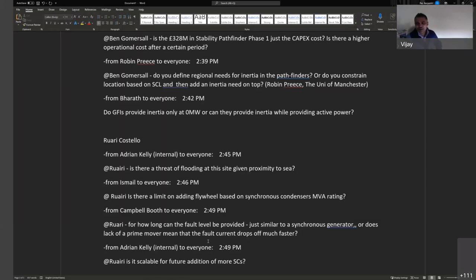How do you start a synchronous compensator? You use a static frequency converter; it's nothing but a synchronous machine. So you basically take the power from the grid, but what you're asking here is that you need some kind of prime mover to rotate the shaft first. So yeah, you need some kind of mechanism. So we use a static frequency converter to start the machine.